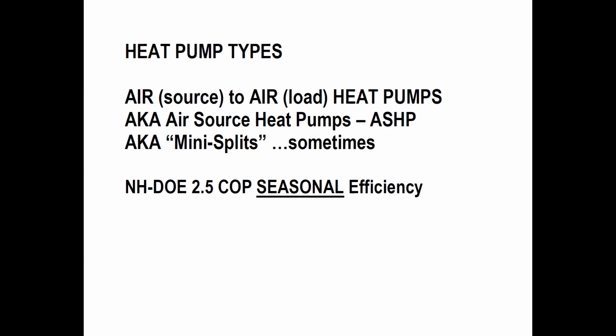All right, this is an important concept of efficiencies. One of the calculations you're going to see later on assumes a 250% efficiency rating. What that means is that for every unit of electricity that I put in, I'm getting 2.5 equivalent energy units out in the delivery to the space. However, with an air source heat pump, because the source temperature goes from minus 13 up to wherever you want heat, 47 degrees or higher, the efficiency varies at all those different temperatures. They're much less efficient down at minus 13 than they are at 47 degrees.